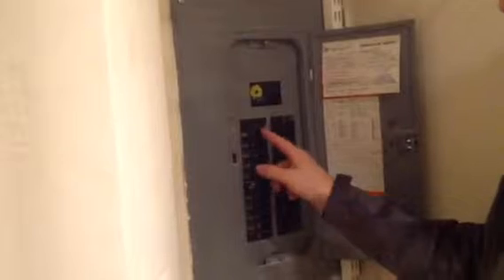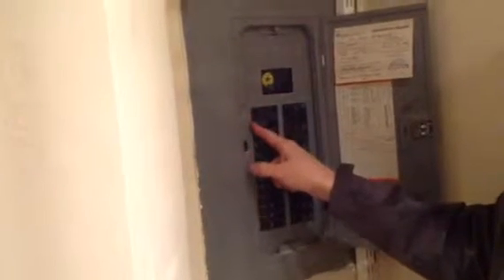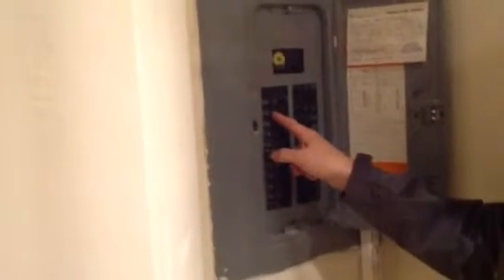Other things with the panel, the 50 amp circuit breaker at the top left section of the panel has undersized electrical wires connected to it. The circuit breaker below that has another double tap where there's multiple wires connected to the circuit breaker. And recommend that the entire panel be evaluated and repaired by a licensed electrician.